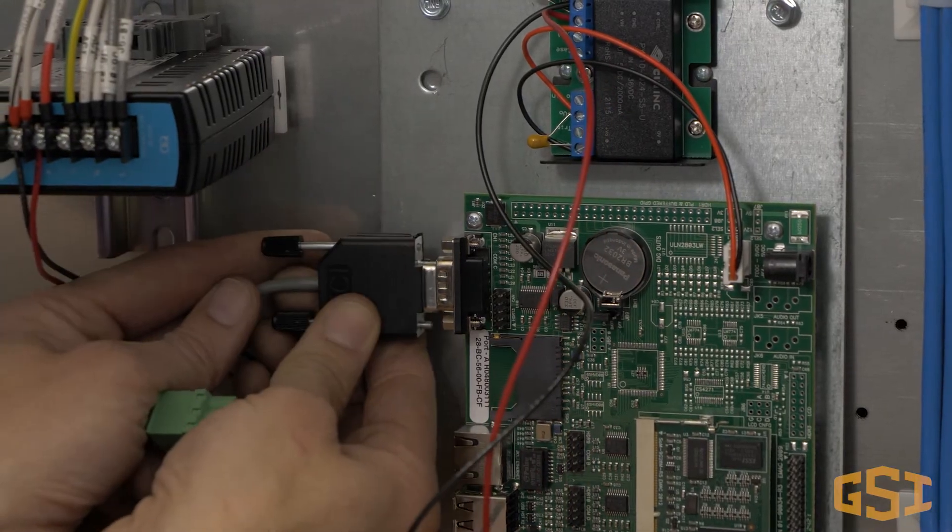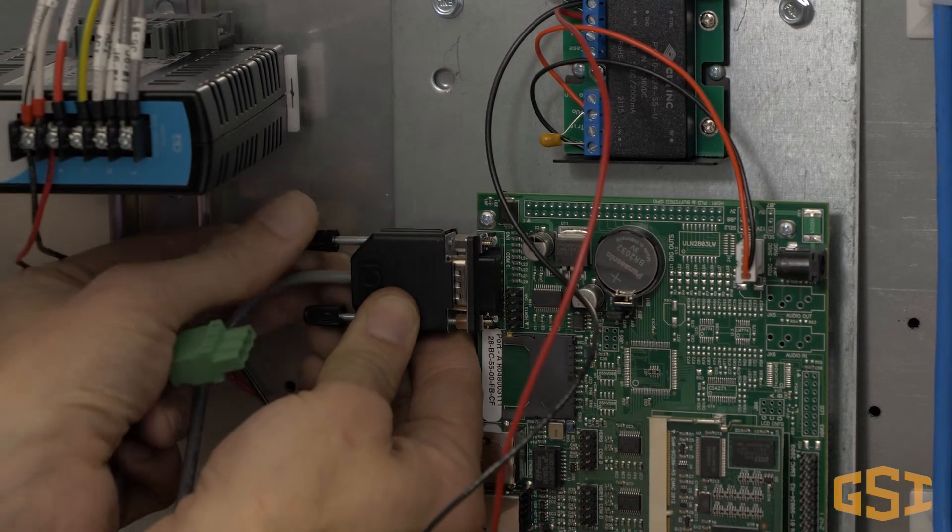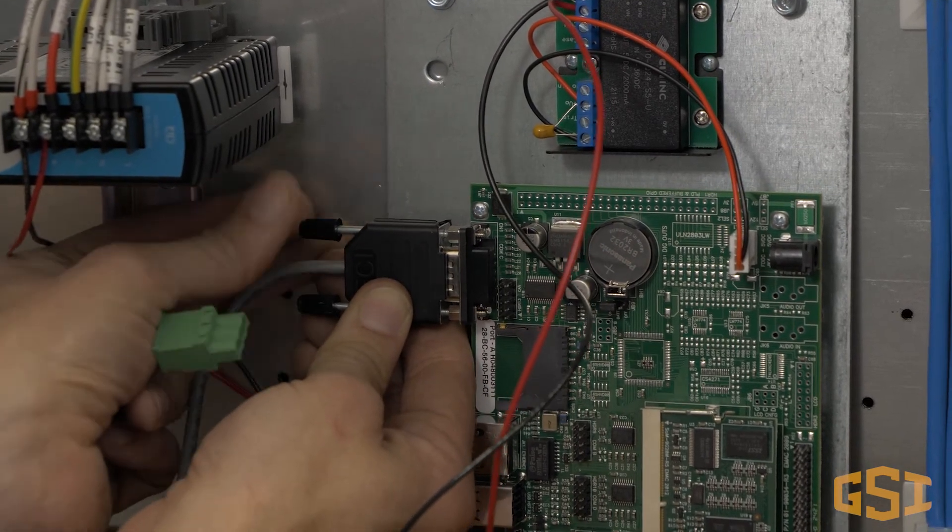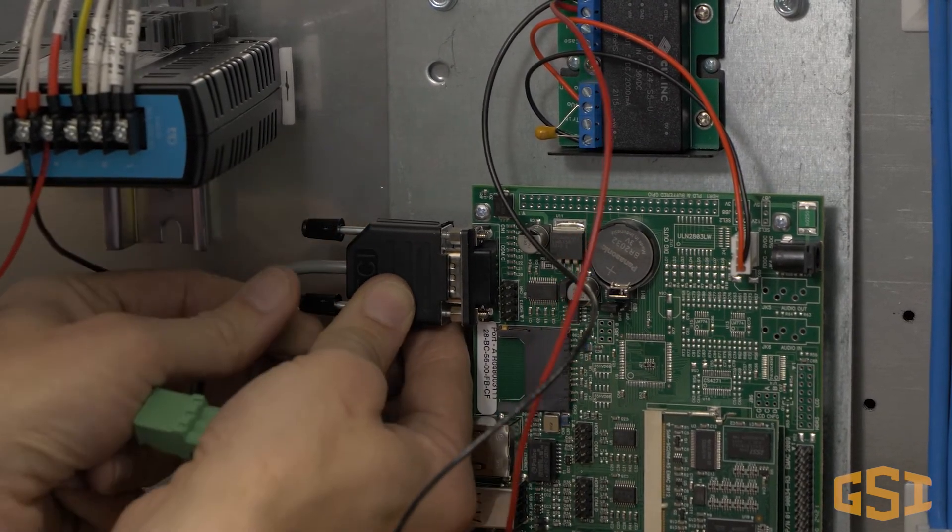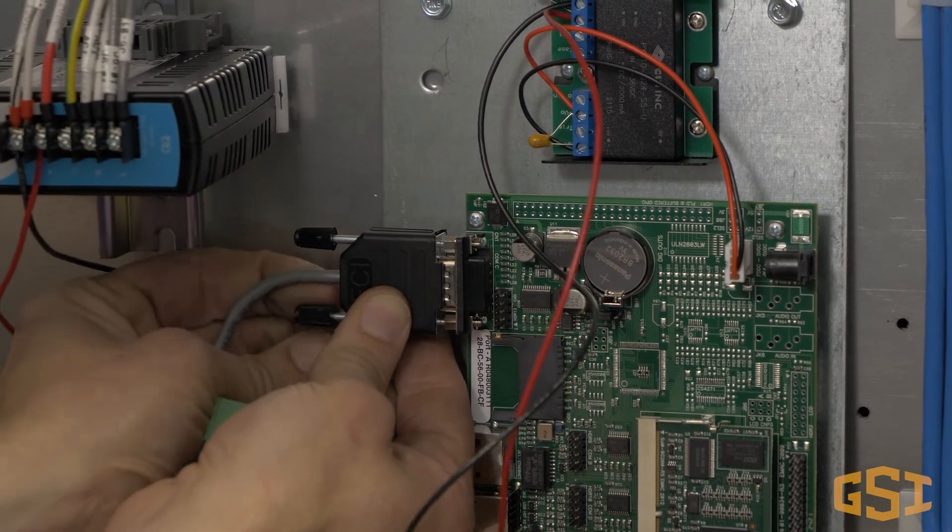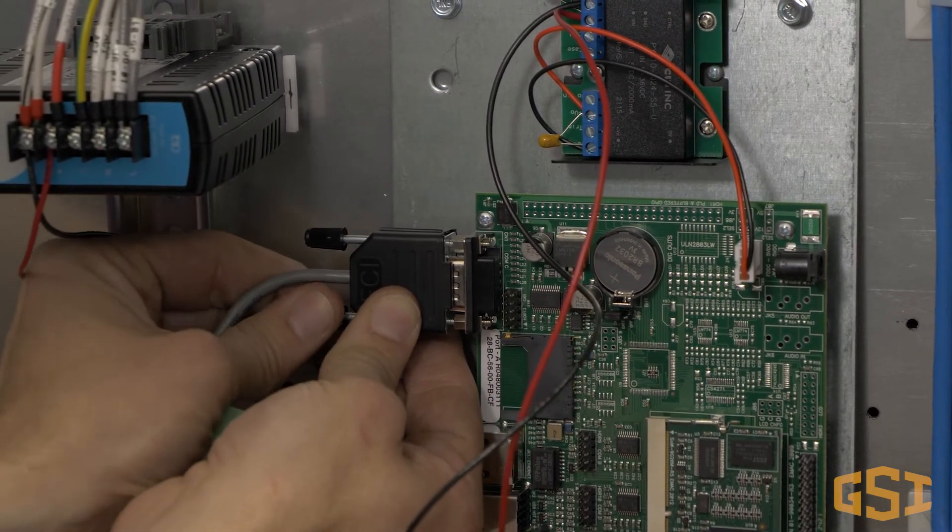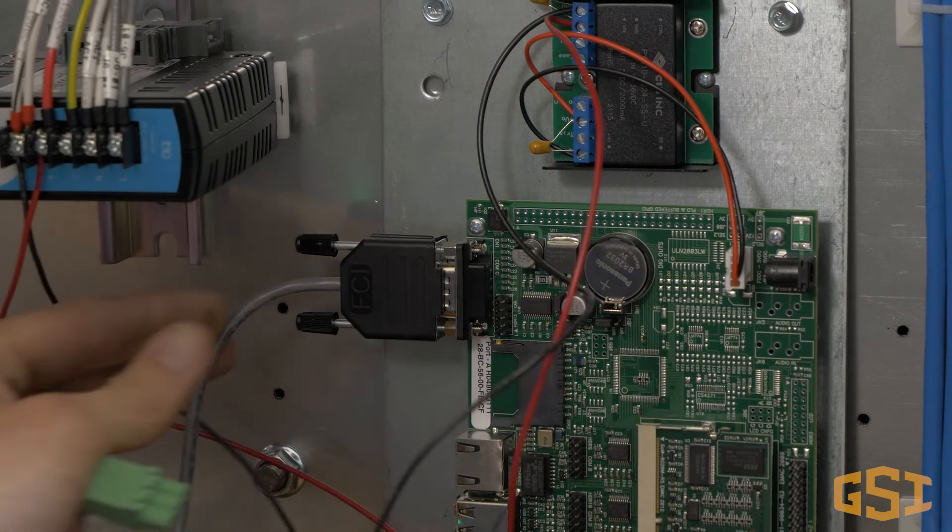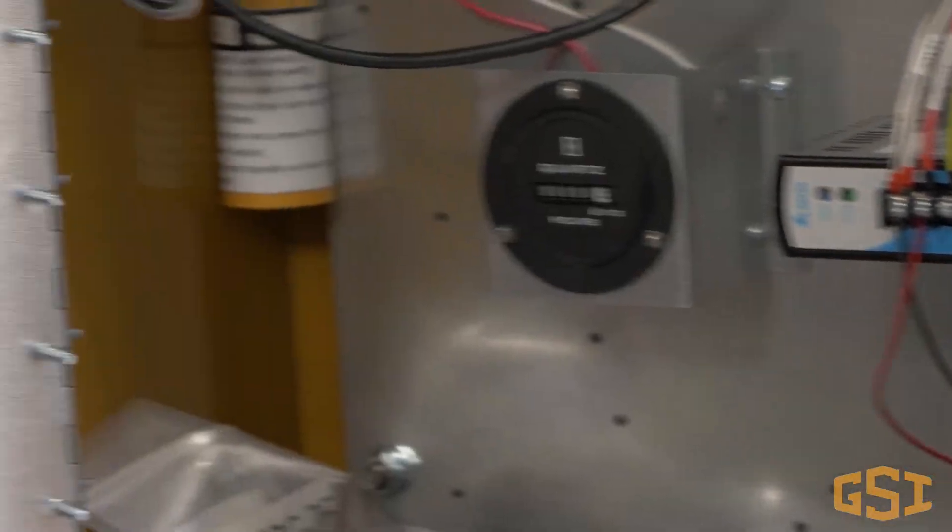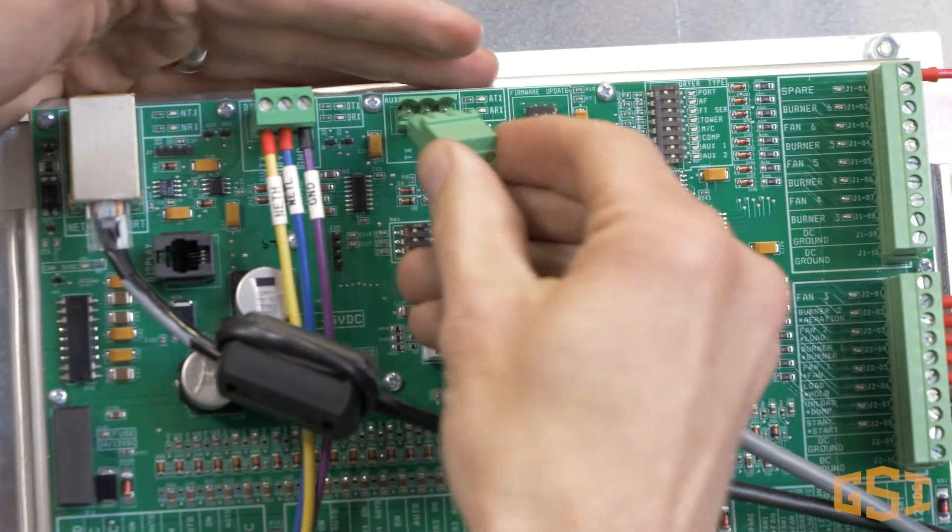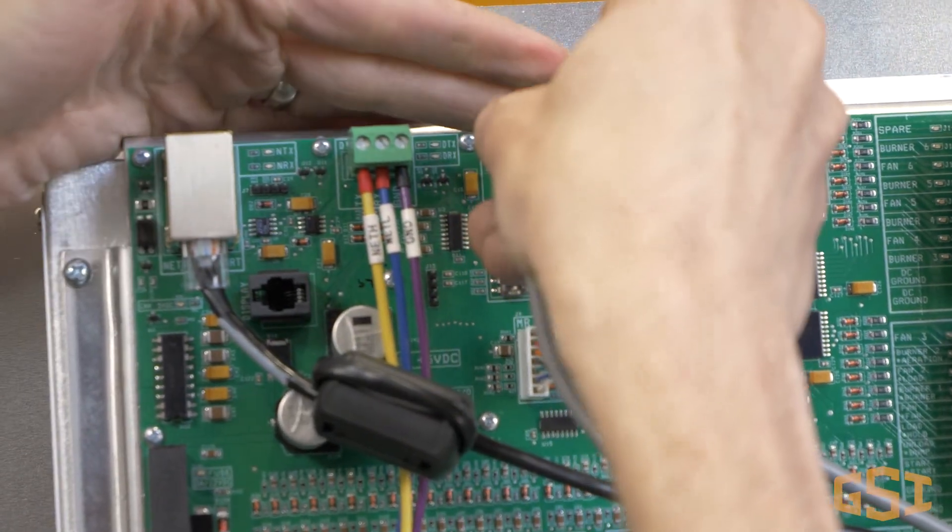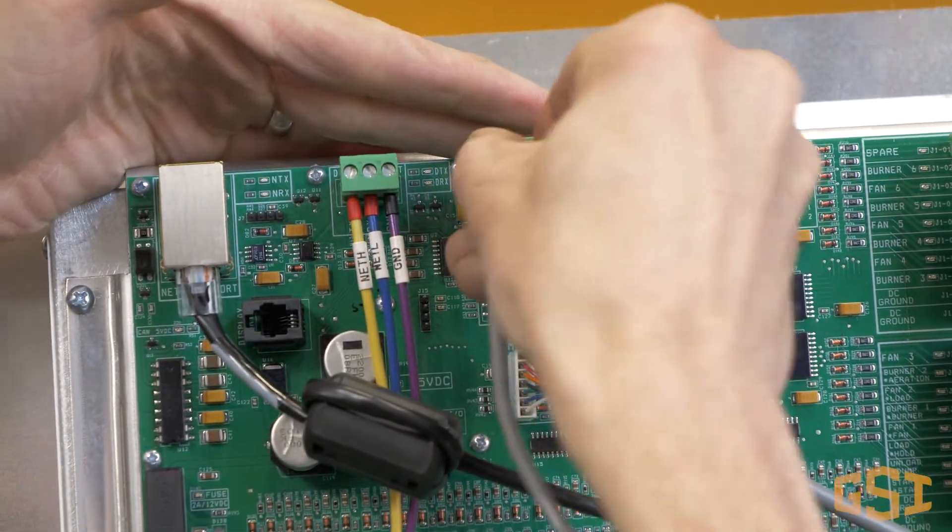Finally, let's connect the Watchdog circuit board to the auxiliary serial port on the display I.O. with the supplied cable. Attach the end of the cable with the DB9 to the corresponding connector on the watchdog board. Now connect the red, white, and black wire with connector on the other end of the cable to the auxiliary serial port on the display I.O. board.